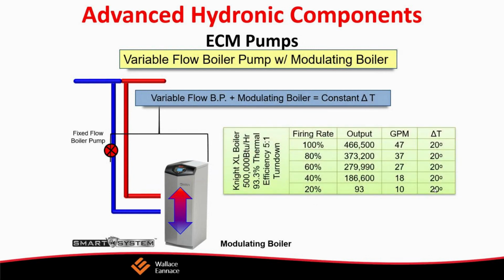Now, one of the things we talked about was the 0 to 10 volt application for these, and I said that it could work in conjunction with the boiler, modulating the boiler down. And here's a really, really important concept. So we have boiler pumps with a modulating boiler, and what happens is when we have a fixed flow pump, we set it for a firing rate of typically 100%.